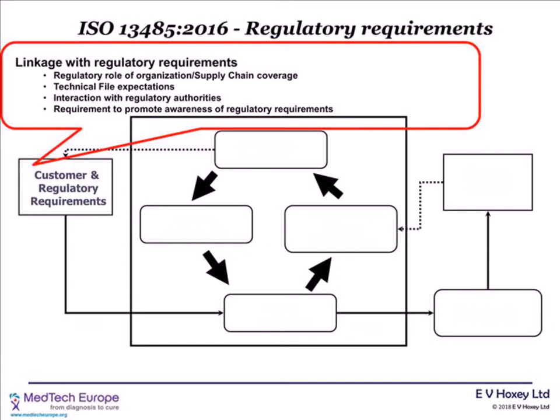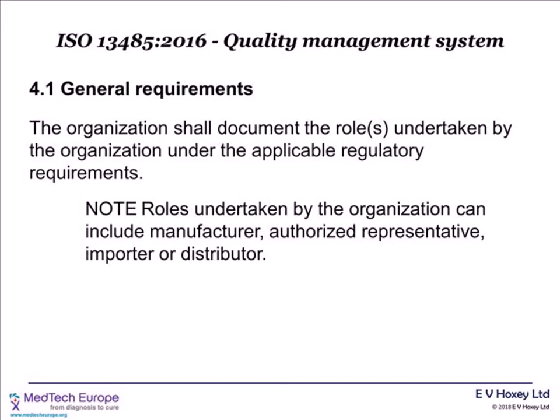So looking at that in more detail, there's now a new requirement in the standard for the organisation to document its role, or roles if it has multiple roles, under applicable regulatory requirements. So it's expecting to see documented somewhere whether the organisation is a manufacturer, an authorised rep, an importer, a distributor, a combination of those, a contract manufacturer, a logistics provider, a design house, an organisation that solely develops specifications for products through design and development. Whatever that regulatory role, in whatever regulations are applicable, it's now requiring that those are documented within the quality management system, that role or those roles.